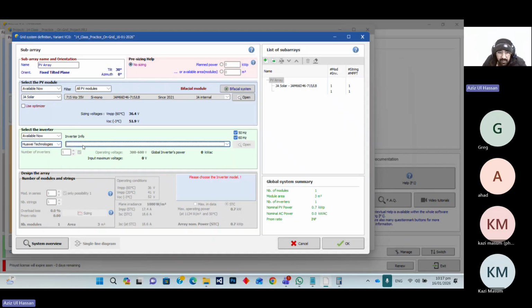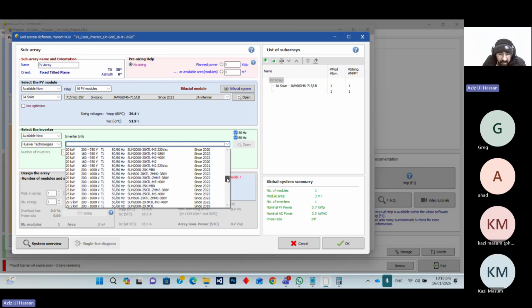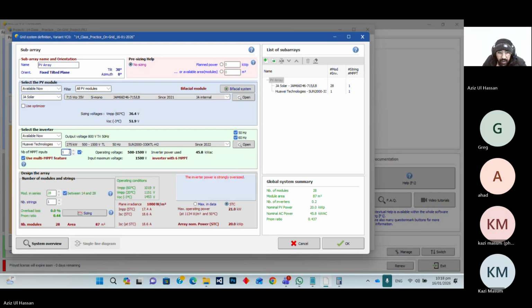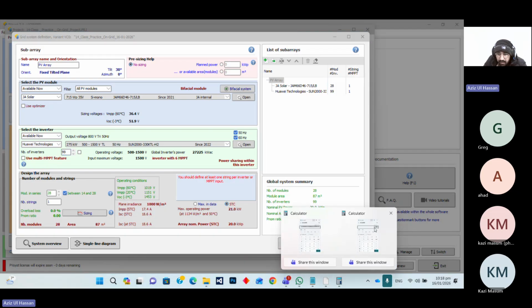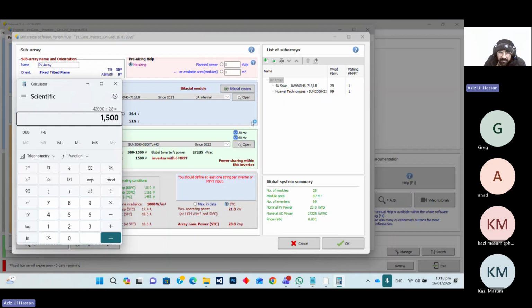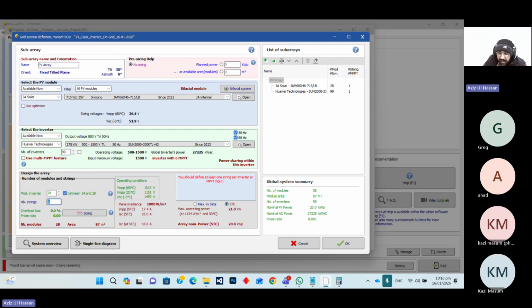I have just selected the Huawei inverters. From Huawei, we have selected these options, like H2, Sun 330 KTL, H2 is the option. And then we have this option. We have selected 99 inverters, with 28 PV modules per string, and 42,000 PV modules there. Divided by 28 means 1500 strings.